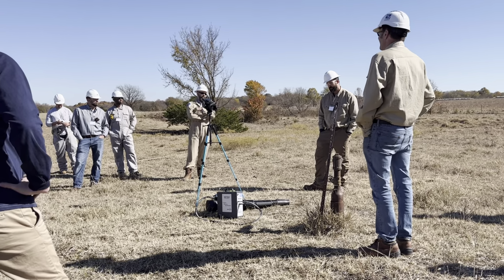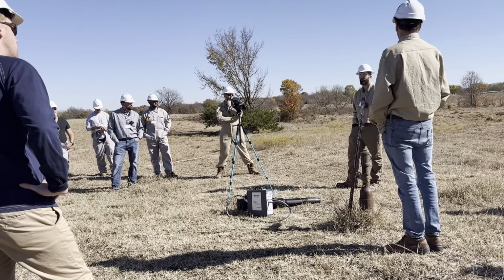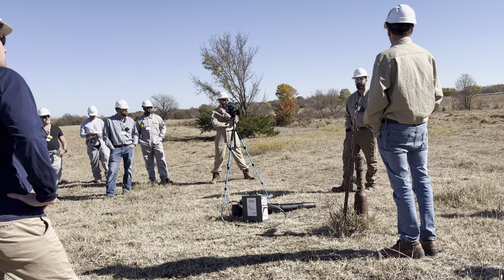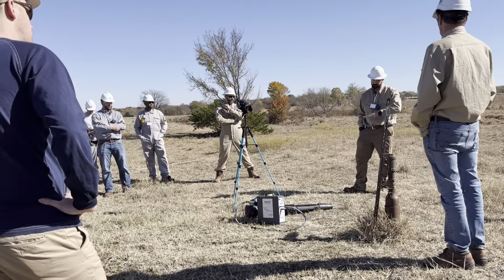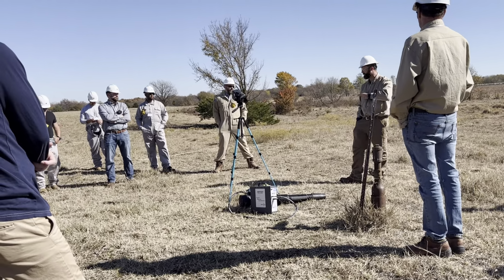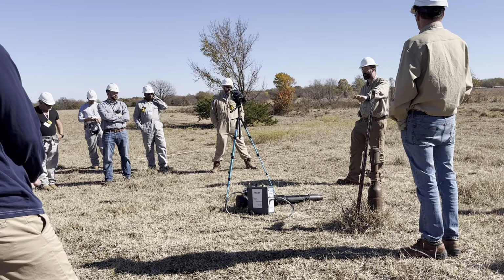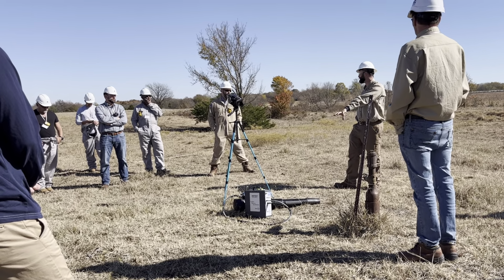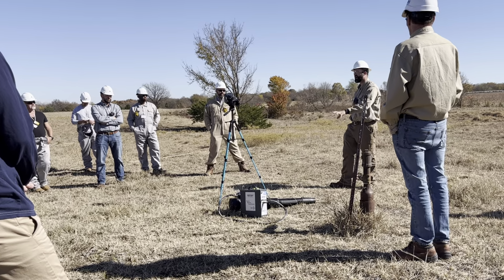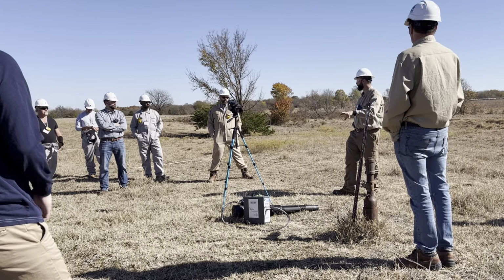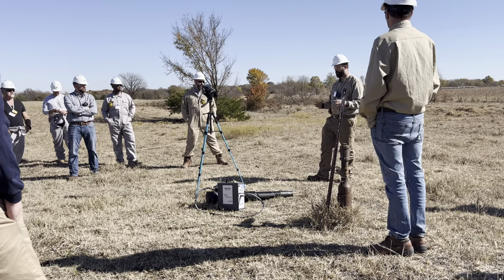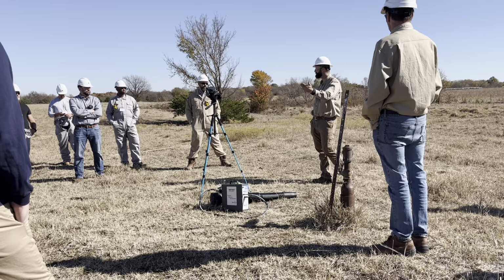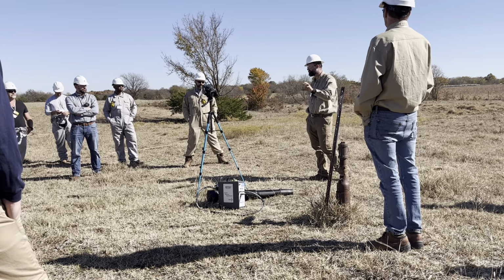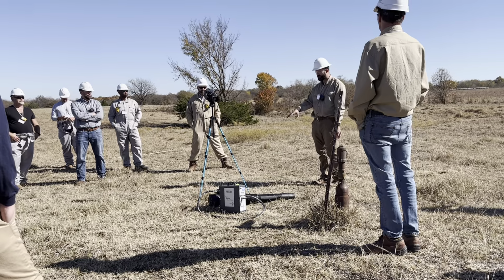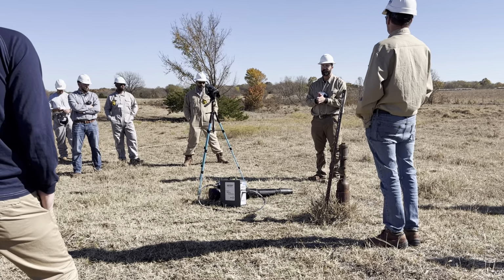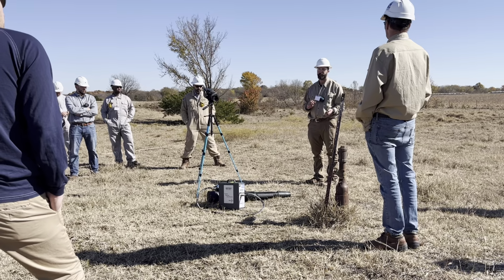The other thing is that, with this being methane specific, it doesn't get cross-contamination from other hydrocarbons and the heavier ones, which we found is really right on the money when it comes to methane emissions. Even though we were quantifying that, there was other stuff in there. Whatever we're reading and measuring here is just methane. I think I mentioned it earlier, but I didn't emphasize it well: we're measuring the whole gas flow, but what's coming out on our register is the volumetric emission rate for methane gas, because just like these lasers, the laser is specific to methane. If we put a propane tank on it, for example, it won't see a thing.